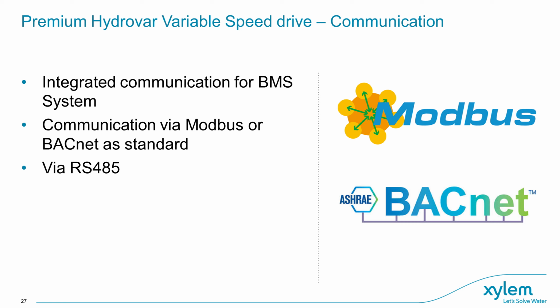The Hydrovar can communicate with local BMS systems through the two most commonly used protocols in building services applications, which is Modbus and BACnet via RS485. This is a standard built-in feature of the Hydrovar and doesn't require any additional hardware.